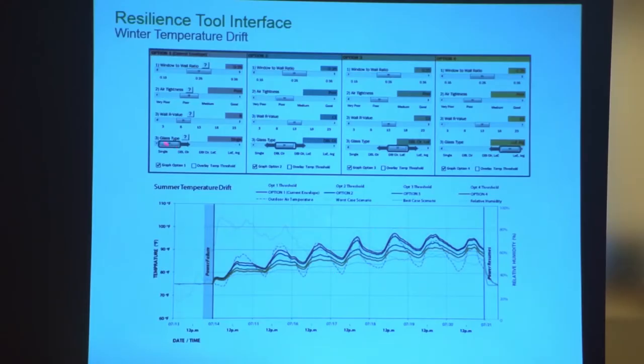In the worst case with a single glazed facade facing south, all these summer cases face south, your peak temperature is matching or exceeding the outside air peak temperature. So minimizing those gains and shading any exposed thermal mass of the wall allows you to stabilize and slowly gain.